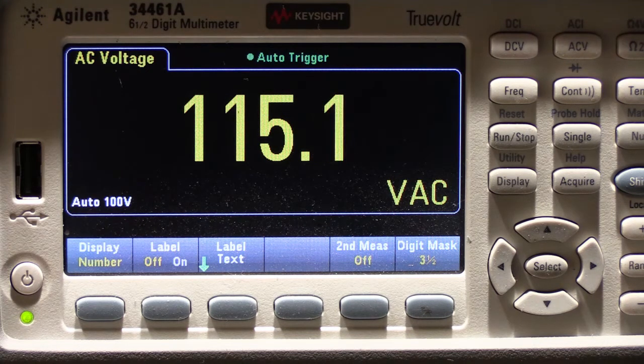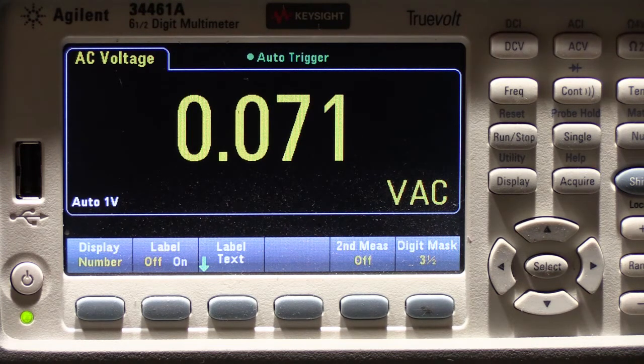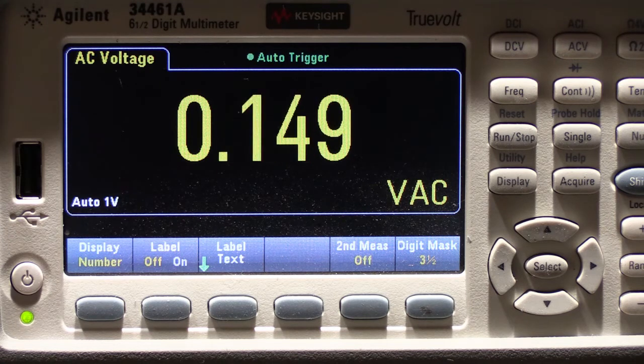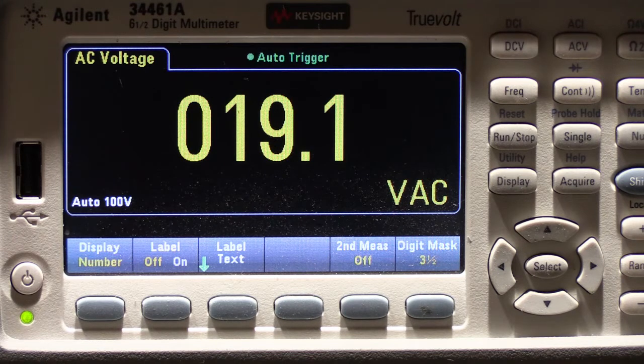Okay, that's pretty close - 115 volts AC line into the transformer. Now I'm putting the probe terminals on the output screws on the secondary side, and we have 19.1 volts, which is well within specifications. We don't know precisely what it was before the original fuse blew, and it's an 18 volt transformer, but 19.1 is fine since there's no load on it, just running free. So now we have a properly working 801T because we've replaced the fuse.